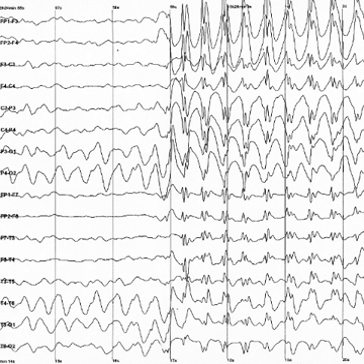The electrode was tested on an electrical test bench and on human subjects in four modalities of EEG activity, namely: 1. Spontaneous EEG, 2. Sensory event-related potentials, 3. Brainstem potentials, and 4. Cognitive event-related potentials. The performance of the dry electrode compared favorably with that of the standard wet electrodes in terms of skin preparation, no gel requirements, and higher signal-to-noise ratio.